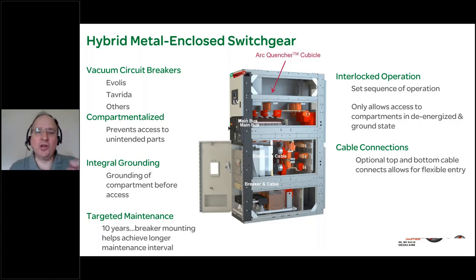So I want to be clear, that is a load break switch. You can absolutely load break with it. However, in terms of the control features, it's desirable from a control point of view, because of the number of operations it's rated for, to have the circuit breaker interrupt the load. So the circuit breaker is electrically interlocked. So if you try to open the switch while energized, the breaker will automatically open. That aux contact from the isolation switch is tied into the breaker's open circuit. Cable connections, top or bottom. We also do side termination when there is insufficient space and we have no rear access.